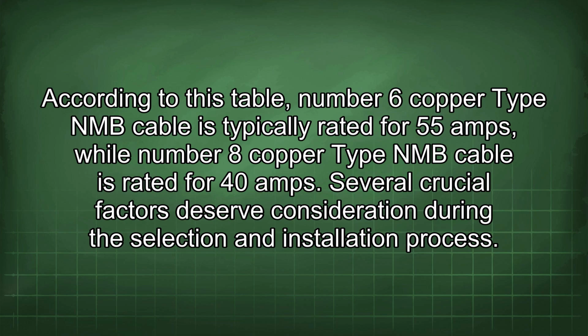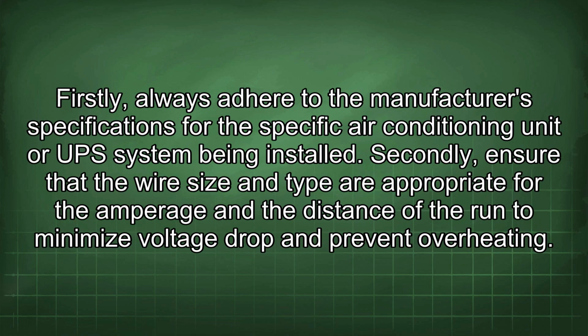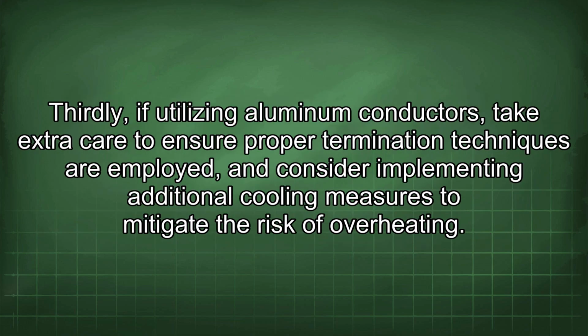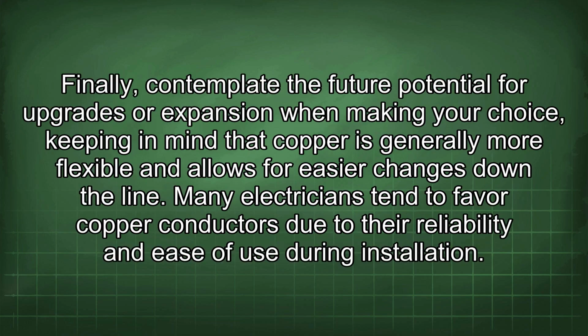Several crucial factors deserve consideration during the selection and installation process. Firstly, always adhere to the manufacturer's specifications for the specific air conditioning unit or UPS system being installed. Secondly, ensure that the wire size and type are appropriate for the amperage and the distance of the run to minimize voltage drop and prevent overheating. Thirdly, if utilizing aluminum conductors, take extra care to ensure proper termination techniques are employed, and consider implementing additional cooling measures to mitigate the risk of overheating. Finally, contemplate the future potential for upgrades or expansion when making your choice, keeping in mind that copper is generally more flexible and allows for easier changes down the line.